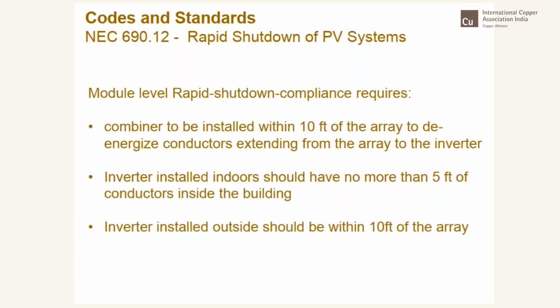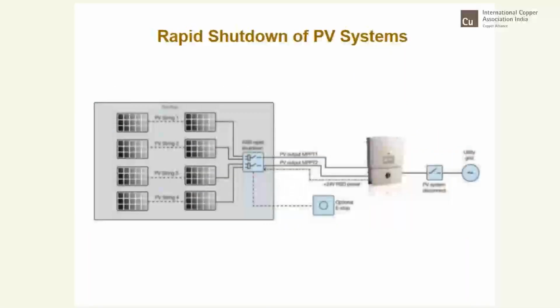This is again for the combiner to be installed within 10 feet, or the conductors to be de-energized. Then an inverter installed indoors should have it too. So these are all specific instructions given in the code. This is how the rapid shutdown system works. As you can see, the light blue in the middle is just after the combiner box. And there are also a lot of very specific rules on how many circuits you can have in a rapid shutdown device. All those things are very clearly mentioned in the NEC code.